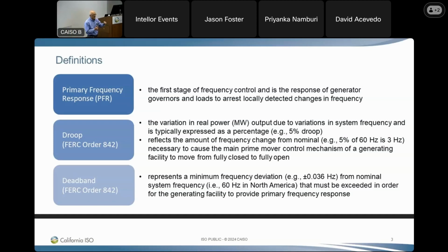And there's a dead band established, and in California it is 0.036 hertz. If the frequency stays within that 0.036 hertz, you're not expected to provide much of a frequency response. That is just to make sure your units are not really gyrating with a change in frequency. And how fast you end up providing frequency response, or what your unit's acceleration is if it goes outside the dead band, is determined by your droop setting.